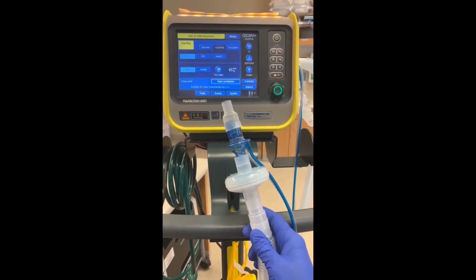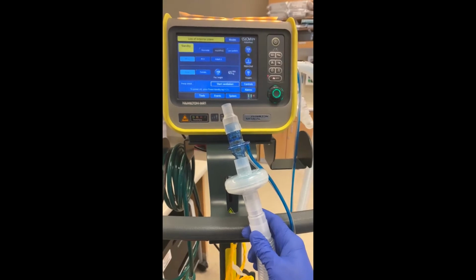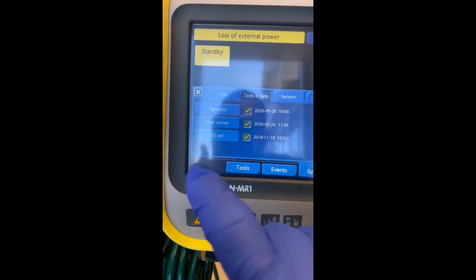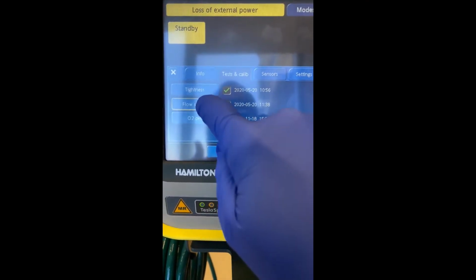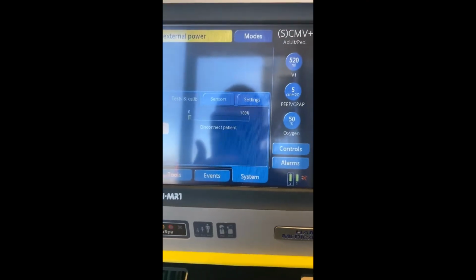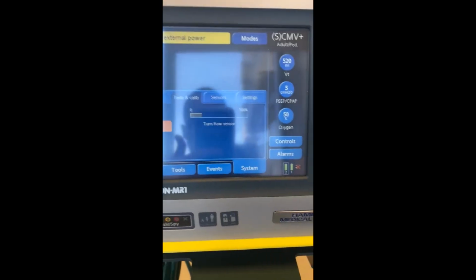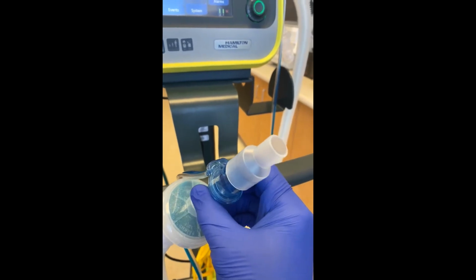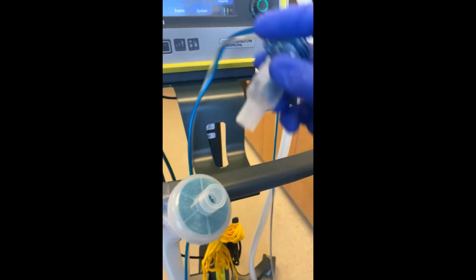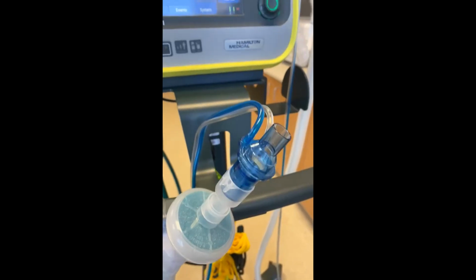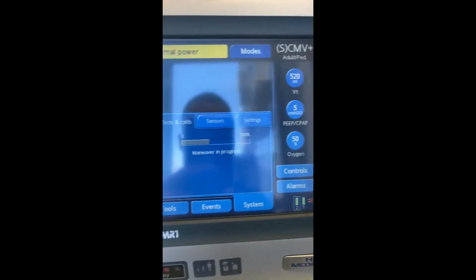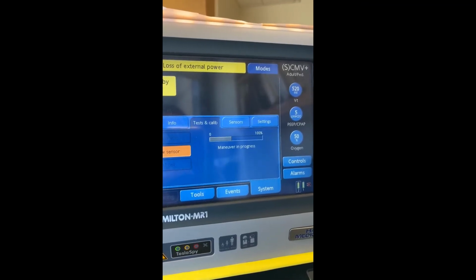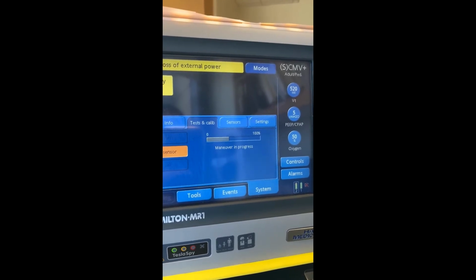And now I'm ready to actually do the flow sensor test. To get to the flow sensor test, you're gonna hit pre-op check and then select flow sensor. It's going to tell you to disconnect patient, which should already be the case, and then turn flow sensor. So you're actually going to take the flow sensor and turn it completely around, just like this. It'll look like that, and then it's going to say maneuver in progress. It'll take a little longer than you think, so just let it run its course.